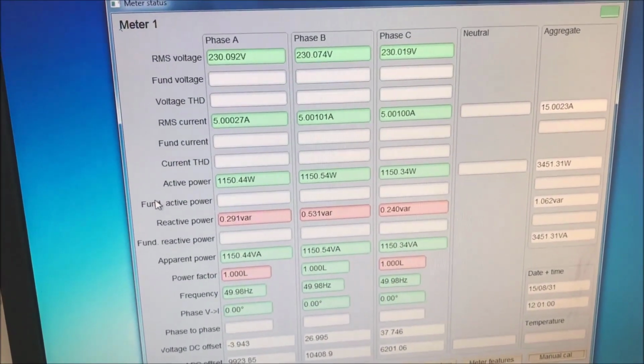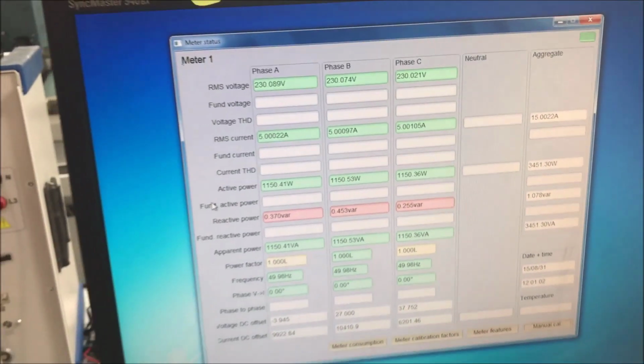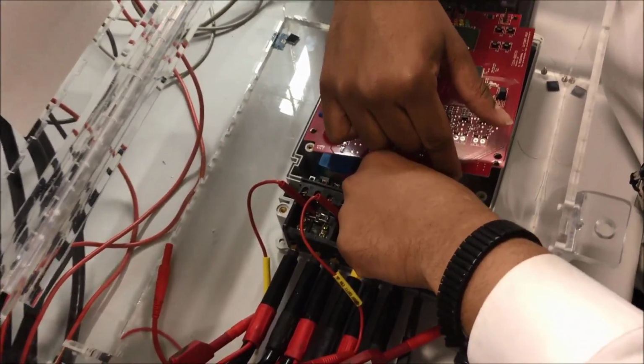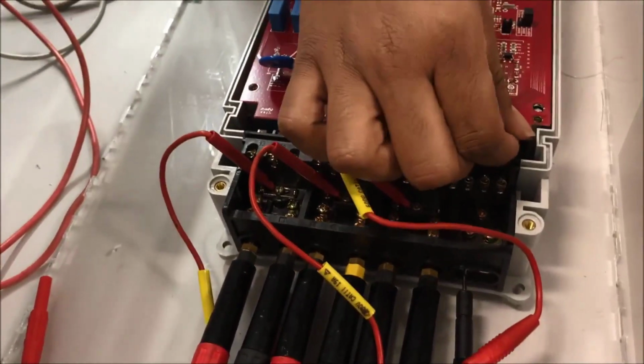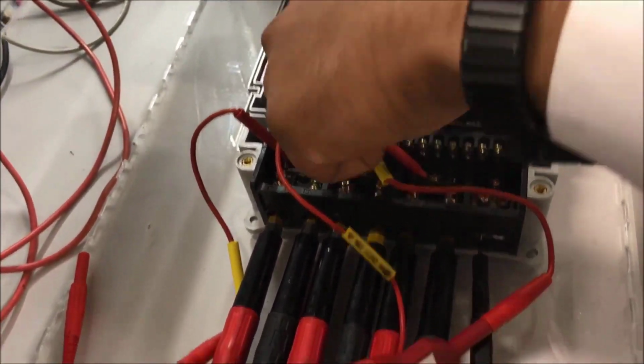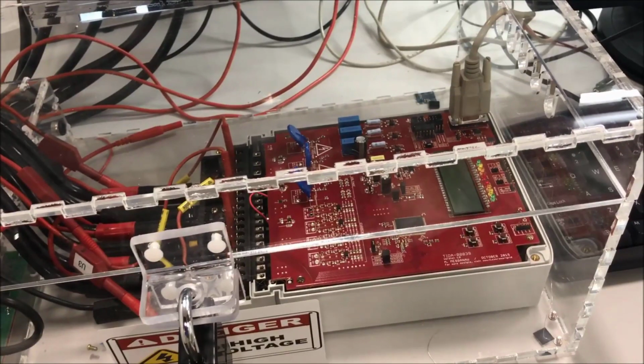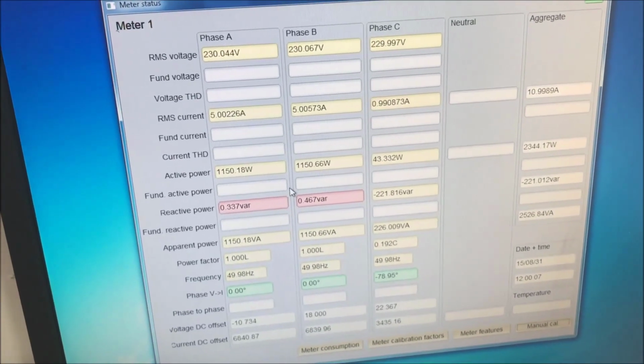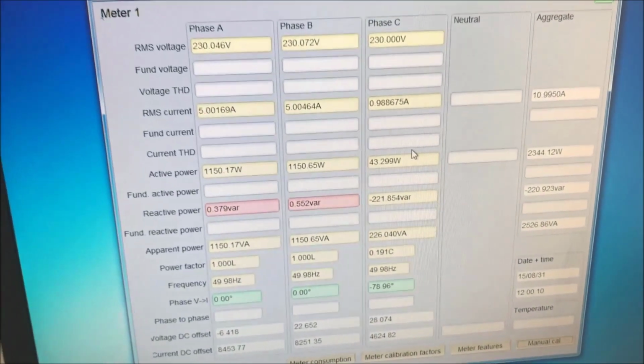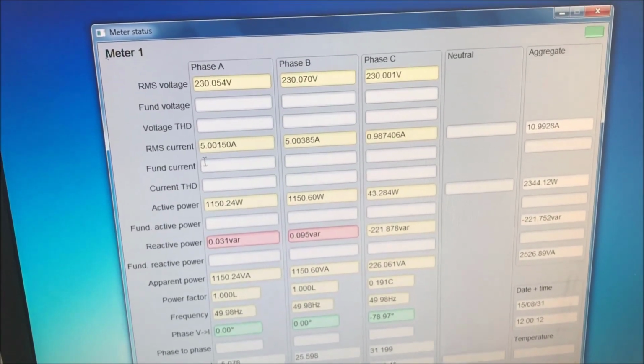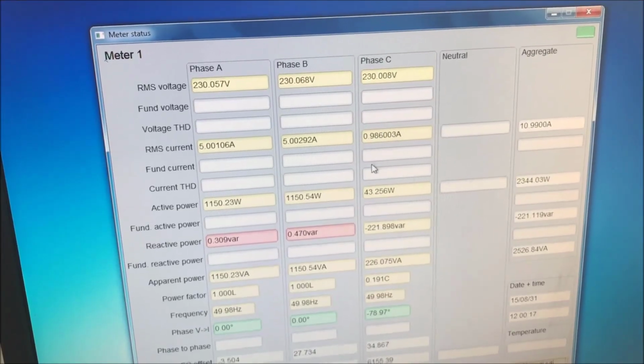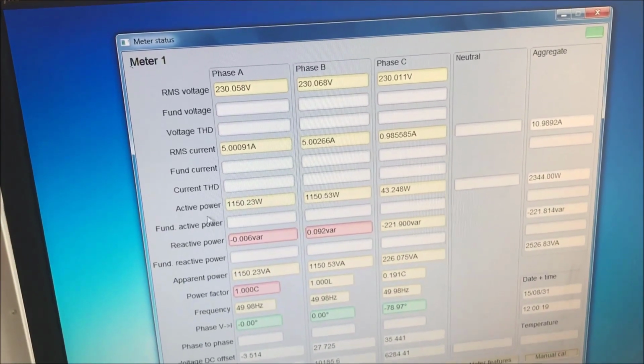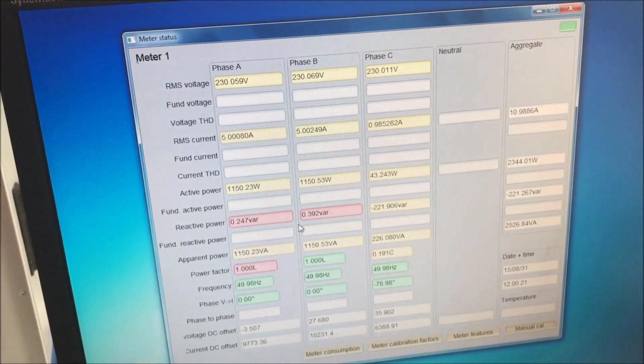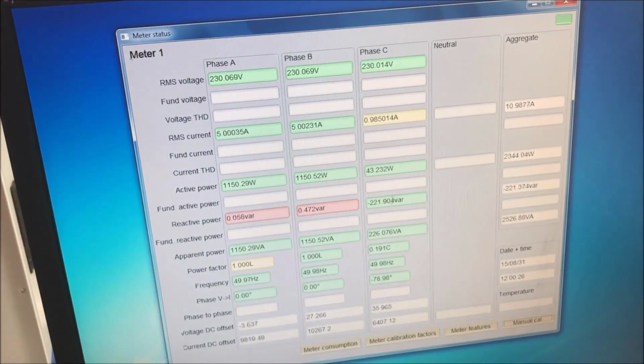Now we'll see how some of these values would change when we apply a magnet on particular CT. For this test, we applied the magnet on top of the CT for phase C. After applying the magnet, we then applied the same 230 volts 5 amp unity power factor conditions. Here we see that the active power readings have decreased for phase C from 1150 watts down to 43 watts. As a result, the consumer will be charged much less electricity than what is actually being used. That is all because of the effect of the magnet on the current transformer current sensor.